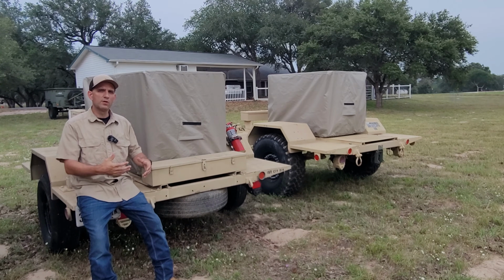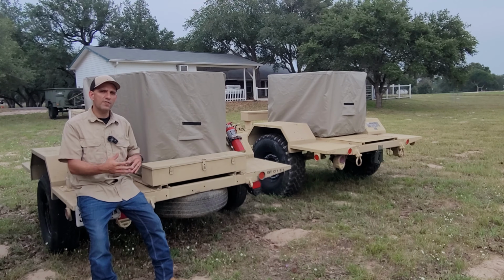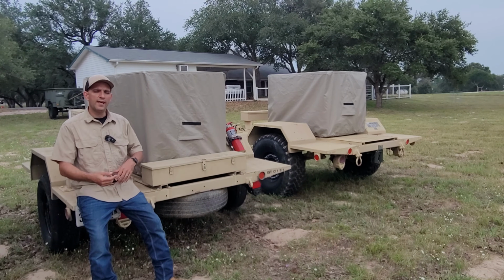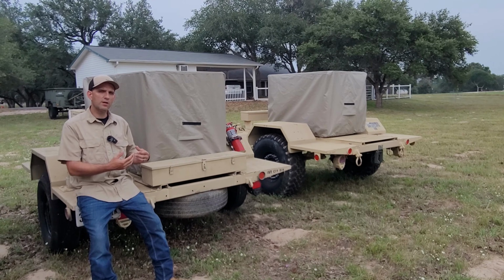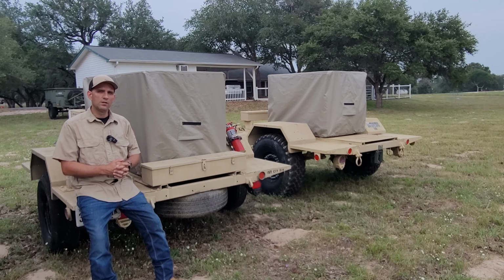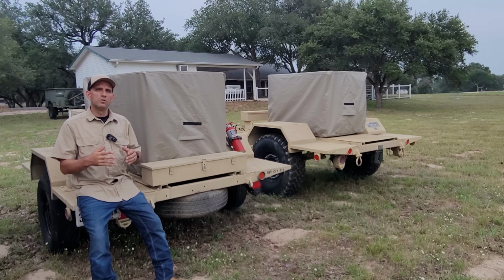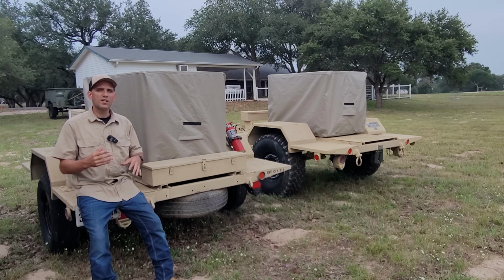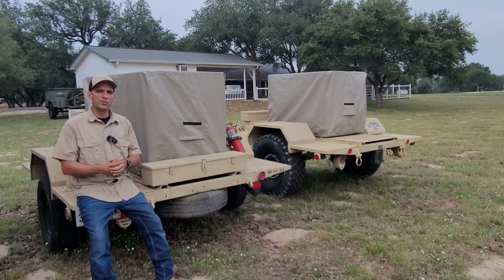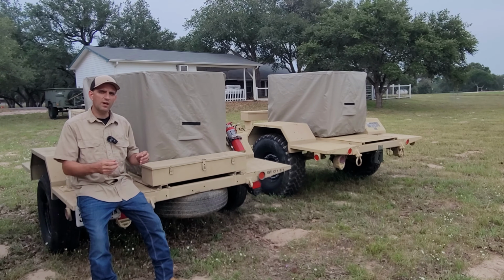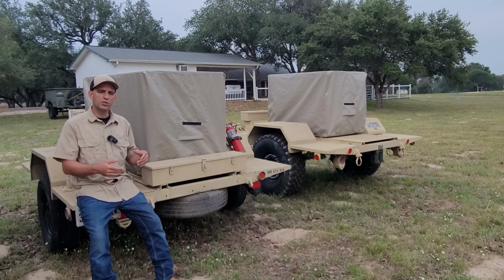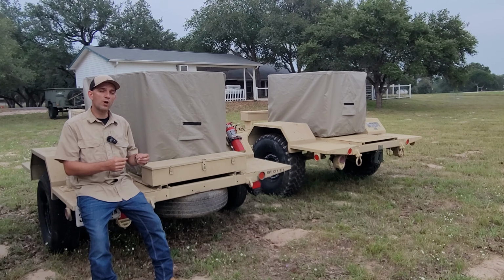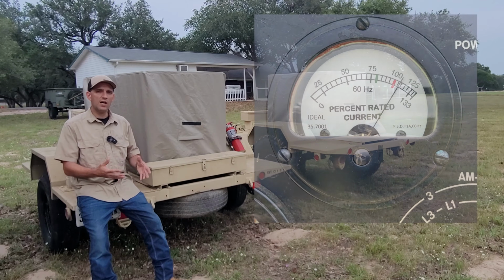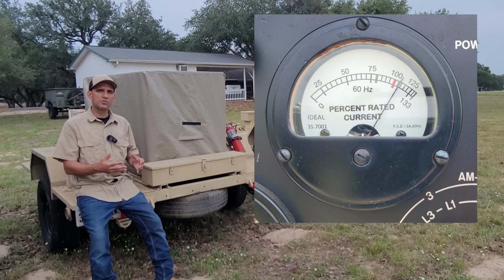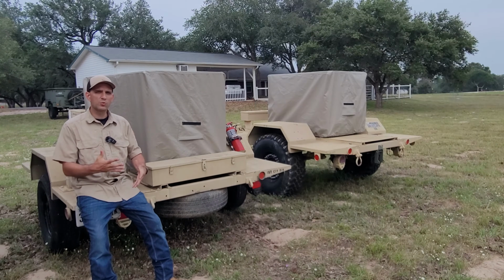If you take the two 5000 watt heaters I showed in my example and load it up, the gauge is going to show about 80% load because it's a 0.8 power factor. So the gauge is true if you know how to read it. With everything I have on my load bank example, it shows a little over 100% on the gauge, but in reality it's a lot over 100%, somewhere close to like 130%. I'll put the exact number up. That's the easiest way to explain it.